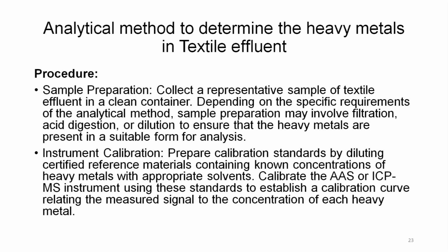And in the case of AAS, it is calibrated with a 4 ppm copper sulphate solution. So, if the known solution shows the expected absorbance, then that means that the machine is well calibrated and can be used for other metal ion identification and quantification.